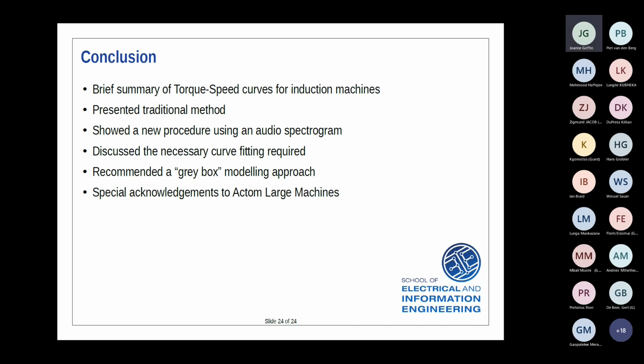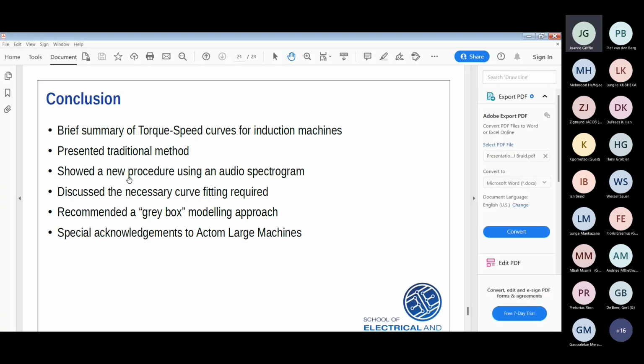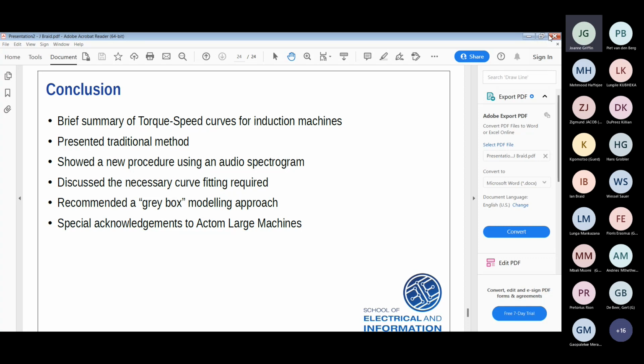The problem is the motions of machines. What you're seeing is it getting closer to speed. Sometimes it'll actually over-accelerate, overspeed, and then come back to synchronous speed, because of the acceleration that is present, so it actually brakes that very last little bit. That's quite interesting. In fact, when you do the speed versus time plot, you can actually see it oscillate, overshoot slightly. You wouldn't be able to pick that up otherwise because the resolution is too low. In this case, using a tacho generator, you can sometimes see that.